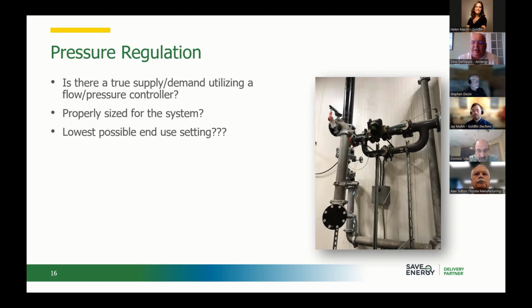Obviously, Steve, you touched on the artificial demand and leakage, but that regulator will actually control the minimum amount of air that we need. And as you choke down on that pressure regulator, and Dominic has seen this happen, you actually reduce the amount of load you put on the compressors.